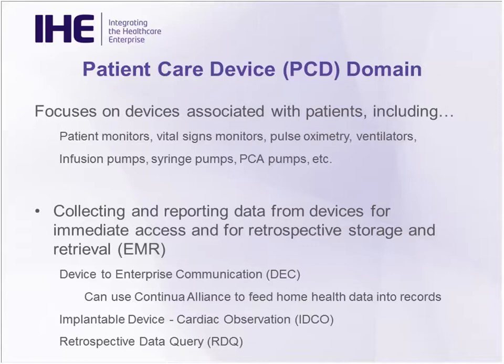We also support a profile that does implantable cardiac observations, so for pacemakers, etc. They're implanted, so obviously they can't do things like network time protocol, but we define profiles that allow gateways to receive the data, include the timestamp information, and then pass that on to the EMR. Once the data is stored, we also have a profile for getting the data back out based upon a query, and that's retrospective data query. Next slide.